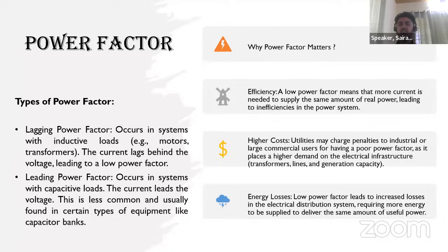This is directly related to the efficiency of the system, how effectively we are using it. If we use the energy that we are consuming to the utmost for getting the output, then the energy cost will also be reduced. If you maintain a poor power factor, then you have to pay more for the contract demand. Your demand will be exceeding, and you will be paying more money to the grid side. You have to get a huge contract demand and pay for it. It also relates to energy loss, the other term for efficiency. If you are inefficient in utilizing the energy that you have bought, then you are losing the energy as a loss.